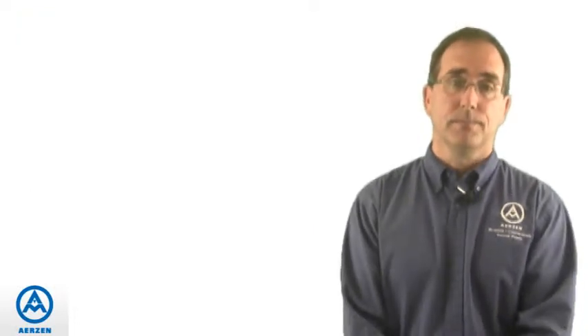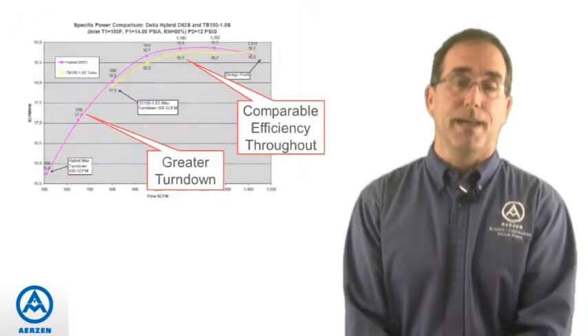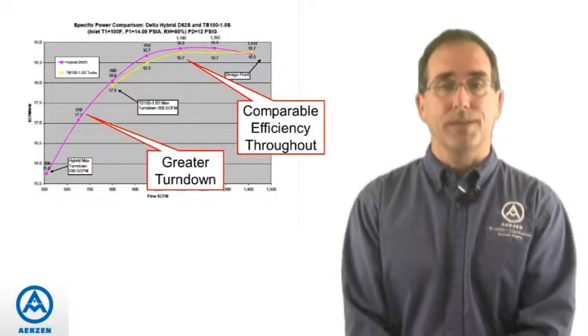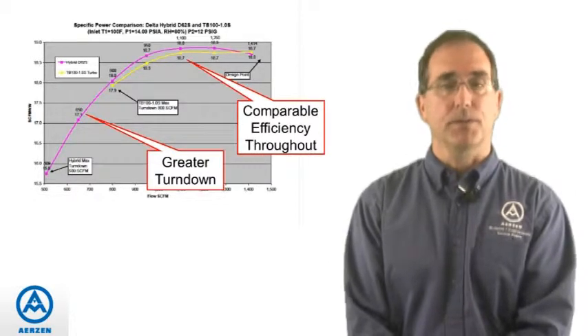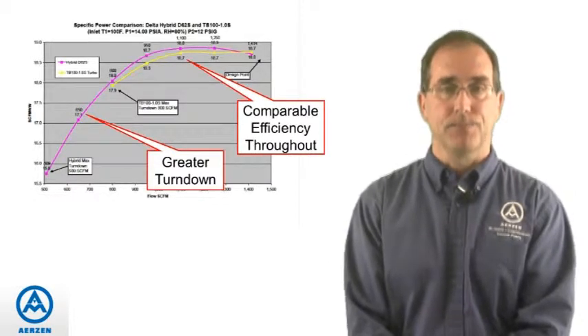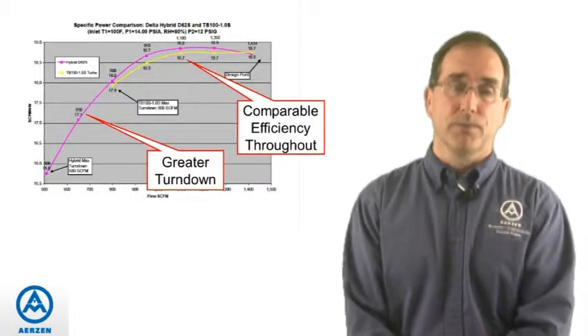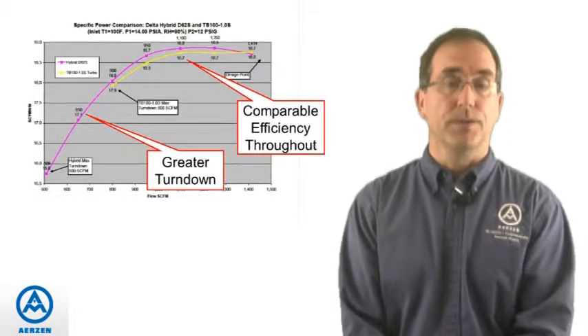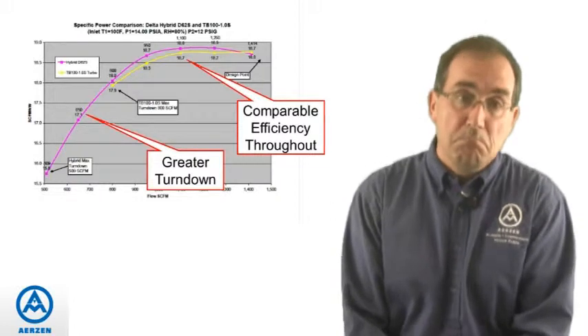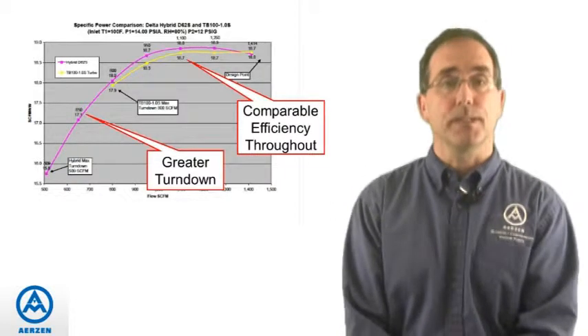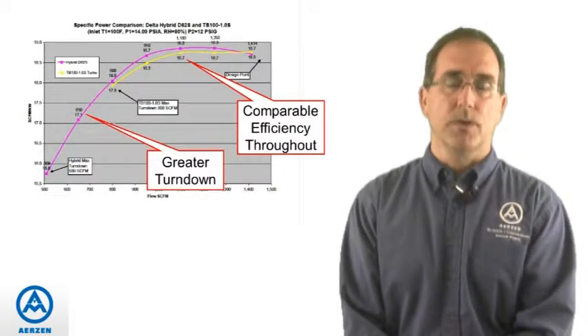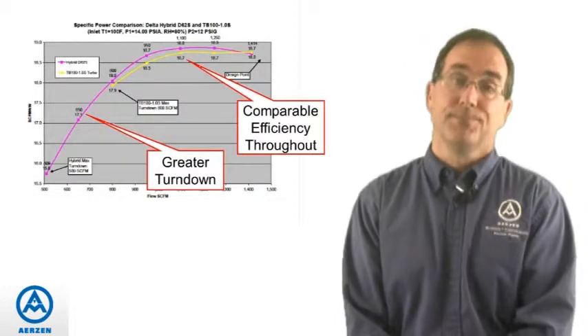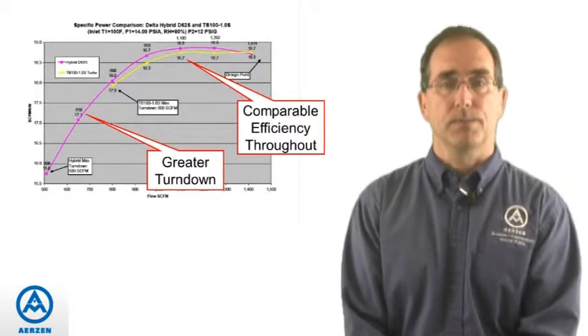In this example, the hybrid and the turbo are pretty much neck and neck with comparable efficiency throughout the entire range. However, if the system calls for a greater level of turndown, the hybrid may be a better choice. If the system is going to run within the range where both blowers lie, then the turbo may be a better choice.